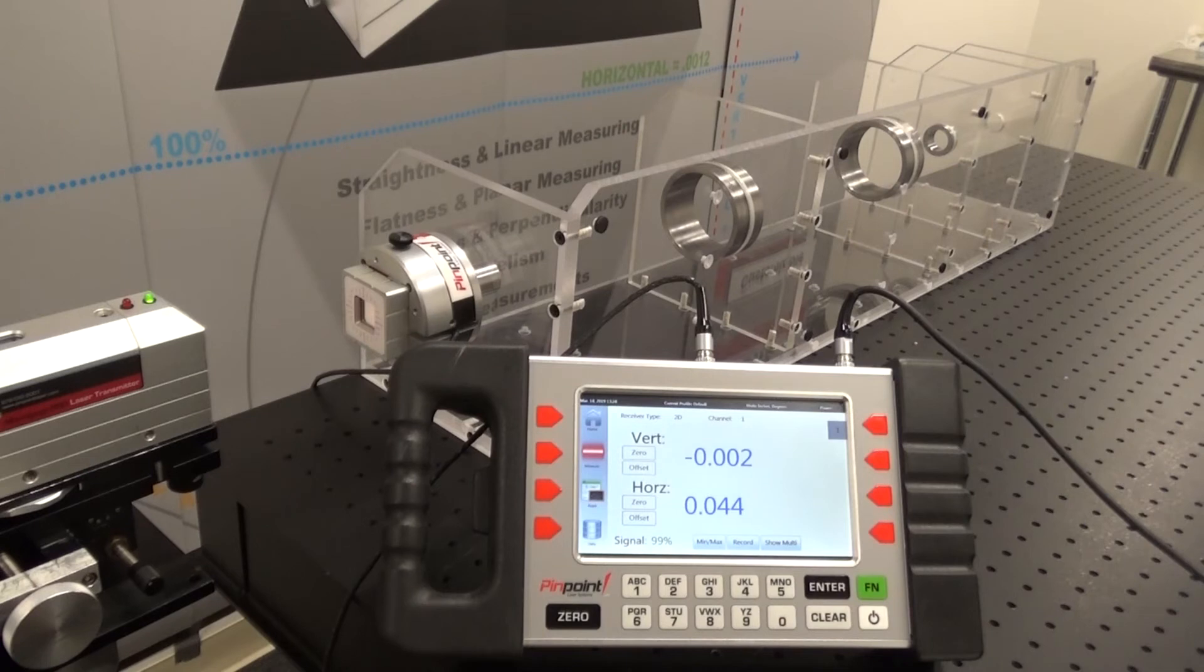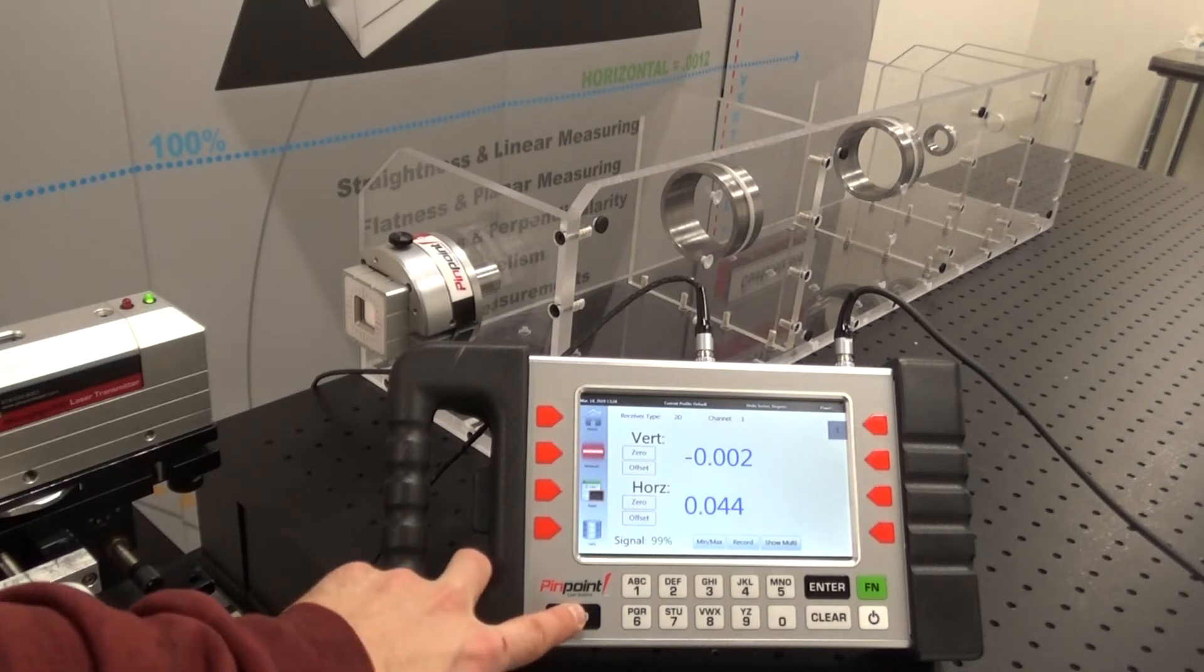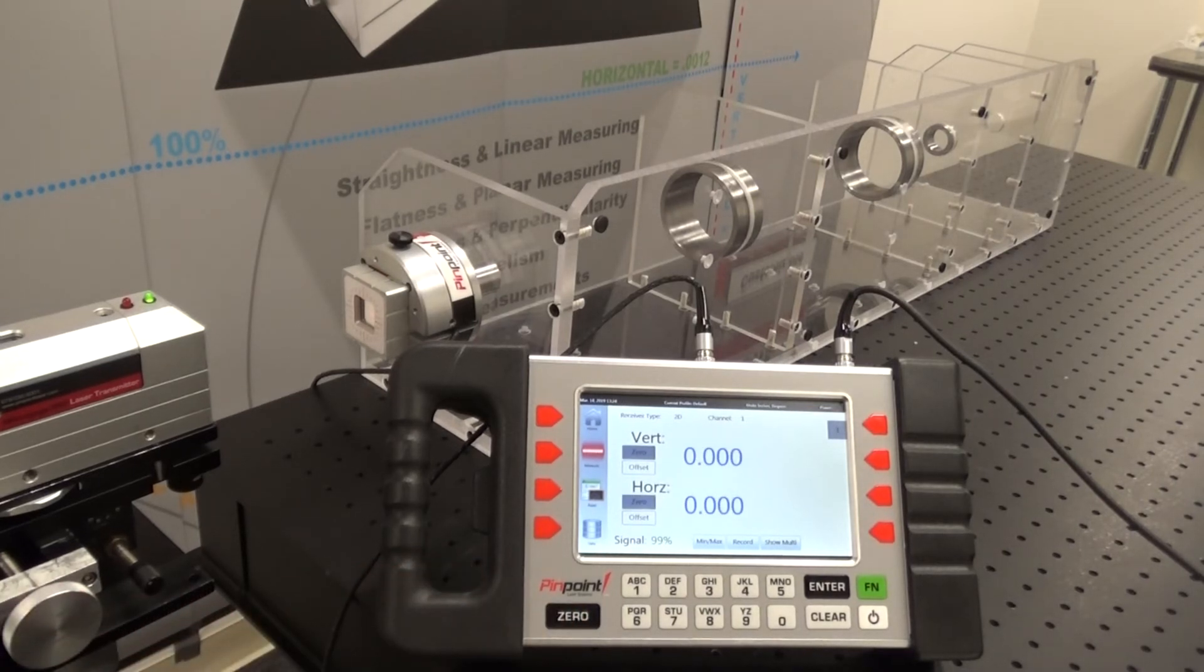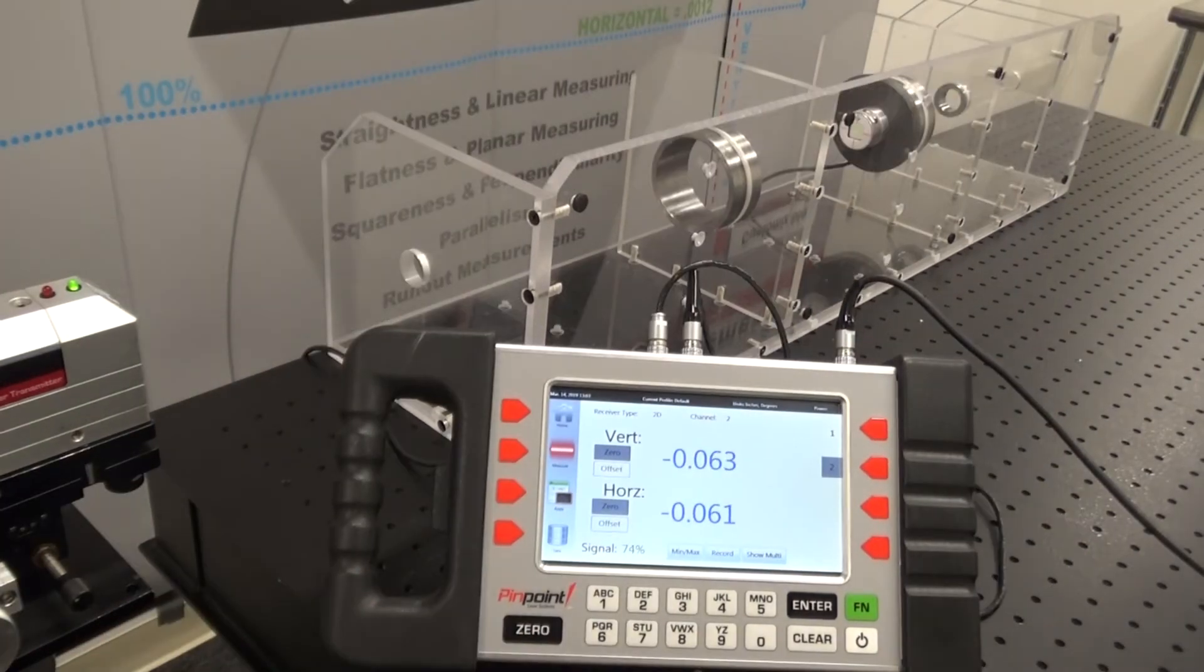Next, we can bring the receiver back to the front bore to confirm alignment. The display indicates that we are bucked in within a thousandth of an inch over the length of the bores. We can zero out the reading and now measure and align all middle bores to this well-established reference line.